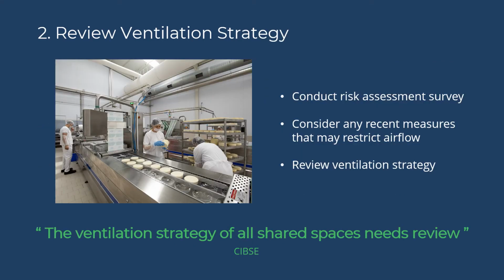The next recommendation is to conduct a review of your ventilation strategy. CIBSE specifies that it is important to conduct a review of all shared spaces. This should start with a risk assessment of your building or production area. And HVDS can provide a risk assessment template based on the BRCGS Food Safety Issue 8 if you would find that useful. The Building Engineering Services Association, BESA, highlights that it is important to consider any measures in this review that might have been implemented over the last few weeks or months in response to the pandemic, which could be restricting the airflow. These might include, for example, the introduction of partitions for social distancing reasons.